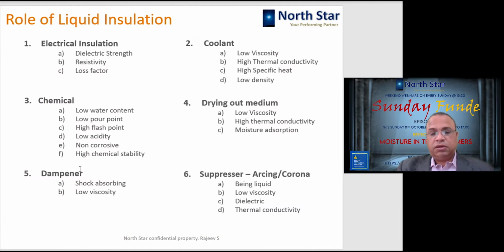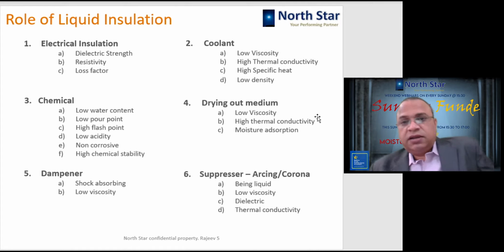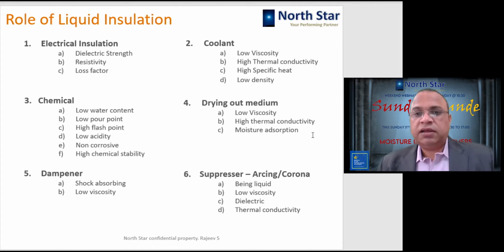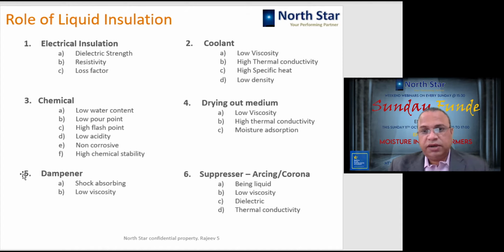Okay, so what is the role of liquid insulation? A liquid insulation plays several roles. One, of course, it is electrical insulation. Then it is a coolant in the transformer. It is an excellent chemical, as it is chemically inert and does not create any corrosion inside. Then it is a drying out medium, because it takes out moisture from the solid insulation, and that moisture is then taken out of the liquid insulation by drying out methods. So it helps in drying out of the transformer.